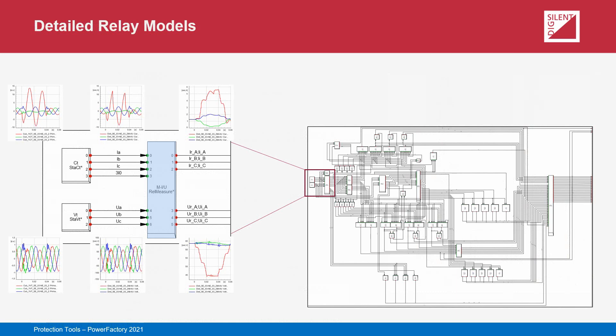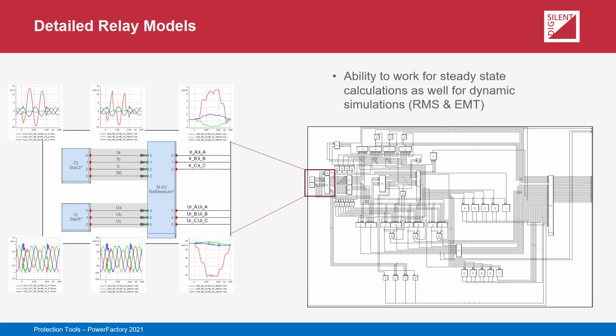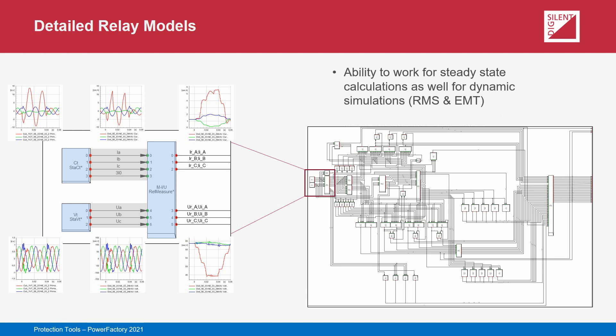As an example, a relay model may contain one or more measurement blocks. The measurement blocks represent the signal processing and conditioning behavior of the real relay. Input signals are provided to the blocks by CT and VT models. For EMT simulation, the block will sample the input signal and extract the fundamental frequency component of the input signal. The calculated values will be assigned to output signals and further processed by the other blocks of the relay model.